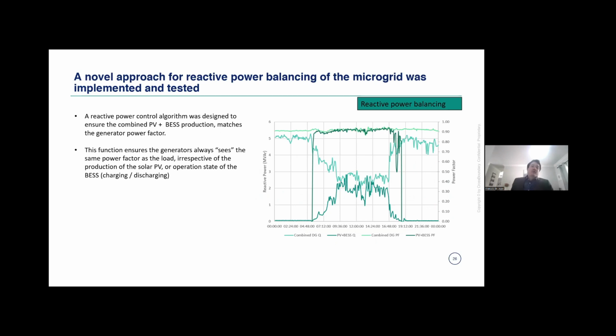So the approach that we applied in order to ensure that we can manage the flow of reactive power across the overhead line while balancing the reactive power supplied by the generators was to essentially apply a dynamic reactive power support functionality, which considers the amount of active power that the solar PV is injecting, the amount of active power that the BESS is injecting or being charged with, and match this with the actual power factor of the load, which is the same power factor that the gensets are seeing. Apologies, this is getting a bit complex, but this was a very interesting part of this project to ensure that we always have sufficient reactive power online and that we are not overcompensating or overexciting any of our assets.